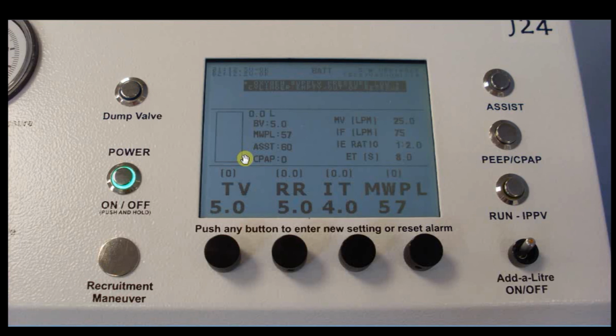So in a normal circle system, you'd have a bag on the circle of maybe say 2 litres, and once that 2 litre bag was full, the pressure would rise, the spill valve would open and the gas would evacuate. So you'd never exceed a bag size of 2 litres because the gas would escape. In Tafonius you can decide your own bag size. So in this instance we have a buffer volume of 5 litres and a tidal volume of 5 litres. Add these two together, we get a total volume of 10 litres.